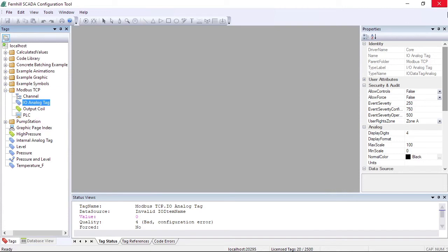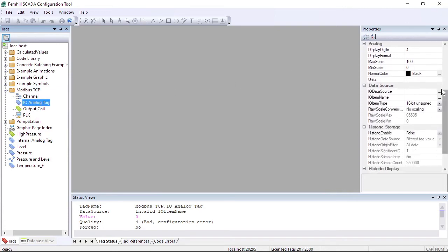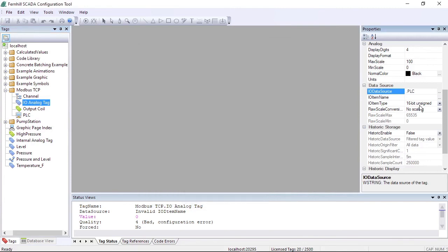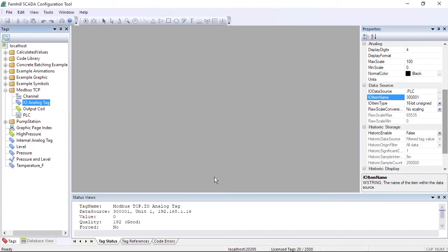We move to the properties window and scroll down. We click the Browse button next to the IO data source and select the PLC we created in a previous step. Then we click the Browse button next to the IO item name field and configure Input Register 1. We can then check the Tag Status window to confirm the quality of the tag is good.